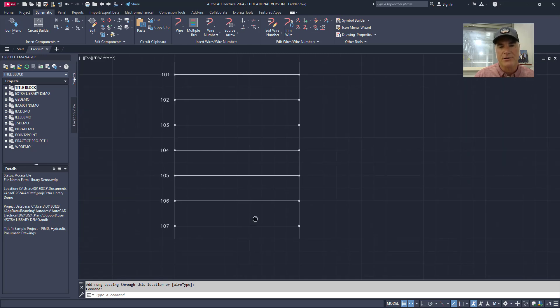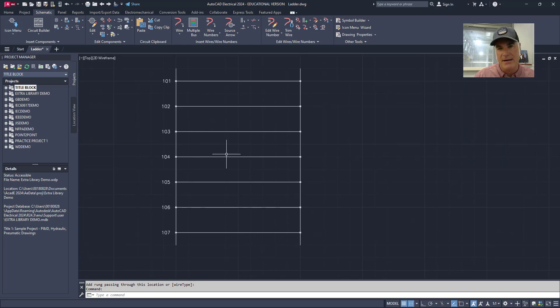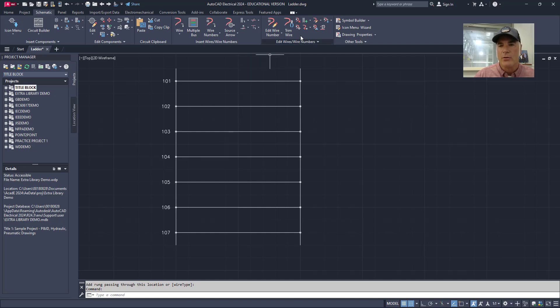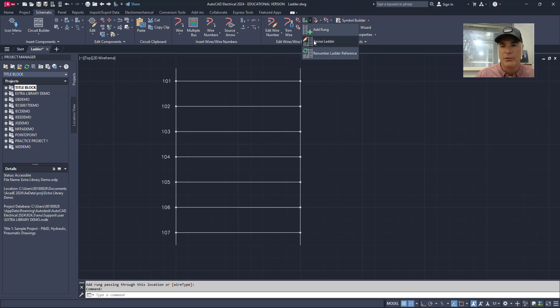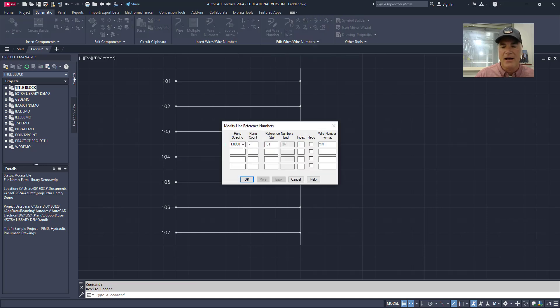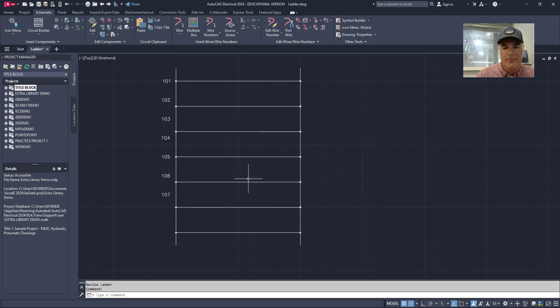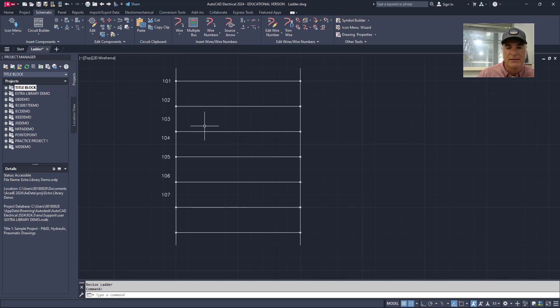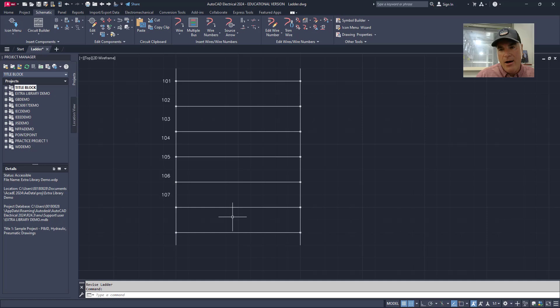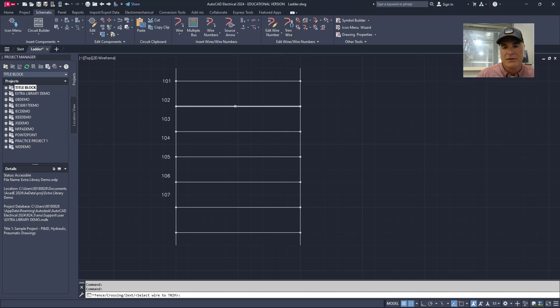Now, if I want to do some other things like change the spacing on these, that's a little bit more complicated, but not terribly complicated. Again, we'll use the revise ladder tool. And let's say that I wanted this still to have seven rungs, but I wanted my rung spacing to be three quarters of an inch instead of one inch. I'll type in .75 and you'll see that it's going to change my ladder. But now what's happened is my numbers are closer together and this rung is in the wrong place as is this one. But this one's okay and then these two are in the wrong place. So what I want to do now is use the trim wire tool. Don't use erase. Use the trim wire tool and trim out the rungs that I don't want.